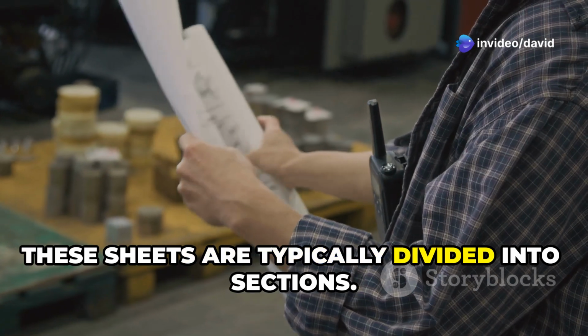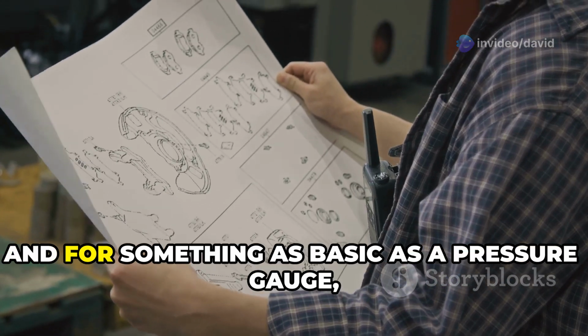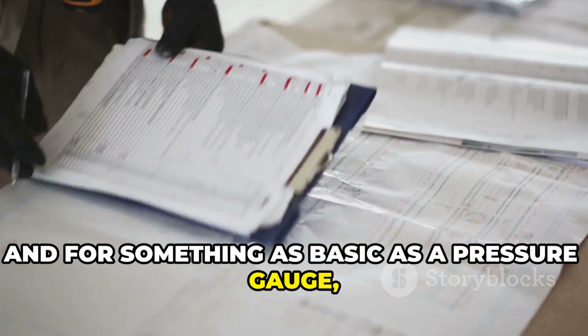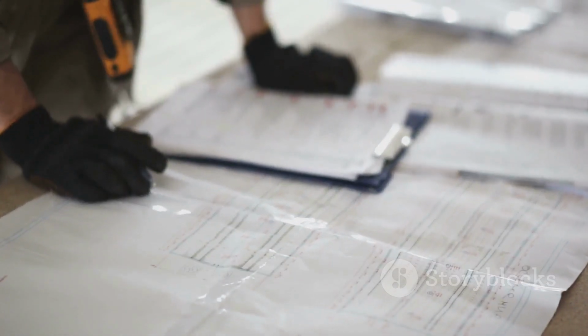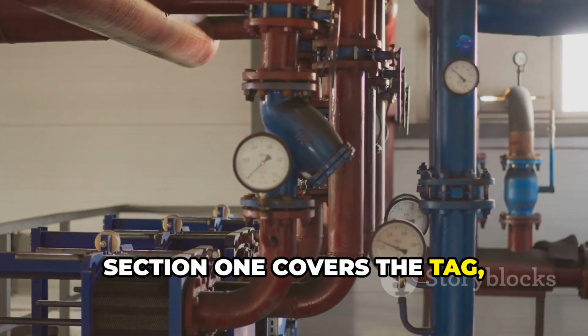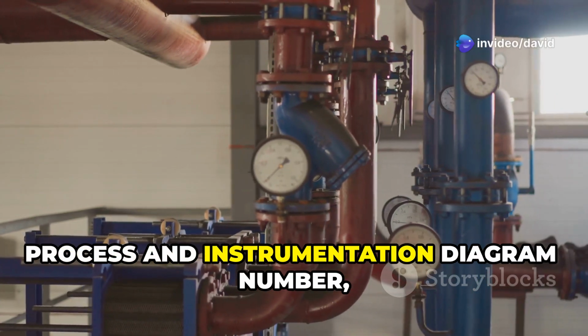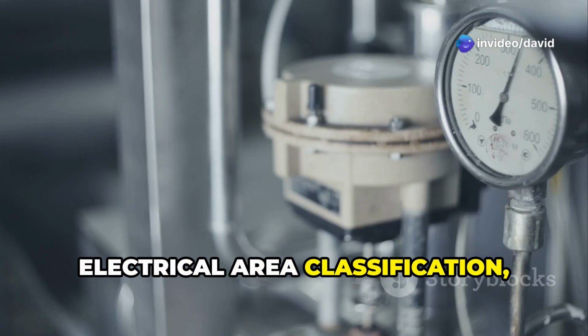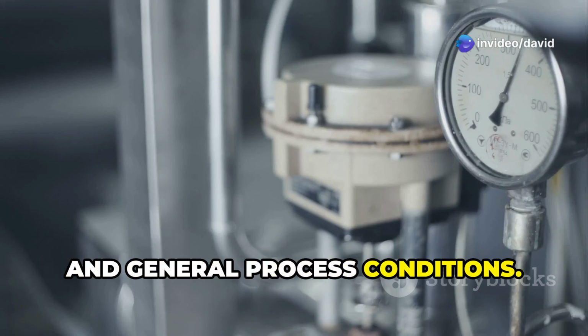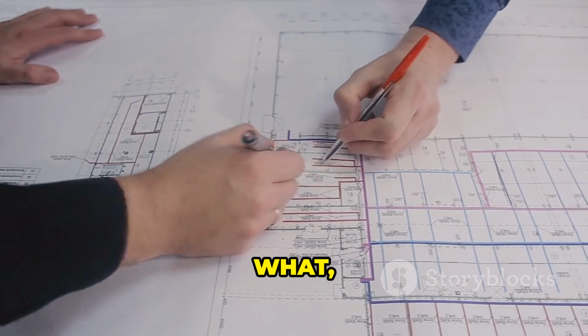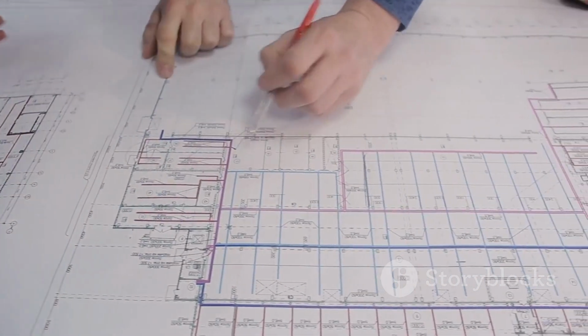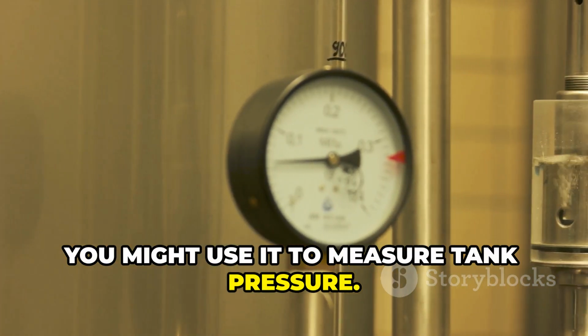These sheets are typically divided into sections. And for something as basic as a pressure gauge, you might see 3 or 4 sections. Section 1 covers the tag, drawing number, process and instrumentation diagram number, electrical area classification, and general process conditions. Think of it as the who, what, where, and why of the gauge. For example, you might use it to measure tank pressure.